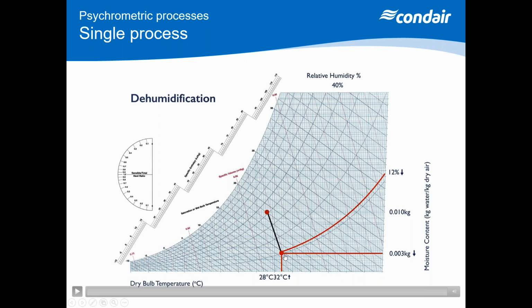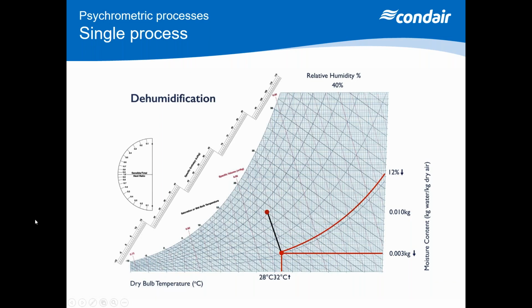Now, if we're doing direct expansion dehumidification, you're going to see a line similar to this. If you're doing desiccant dehumidification, you'll be following the adiabatic process line, which is more along the wet bulb temperature scale. So we have to be careful that we're applying the right psychrometrics to the right method of dehumidification.